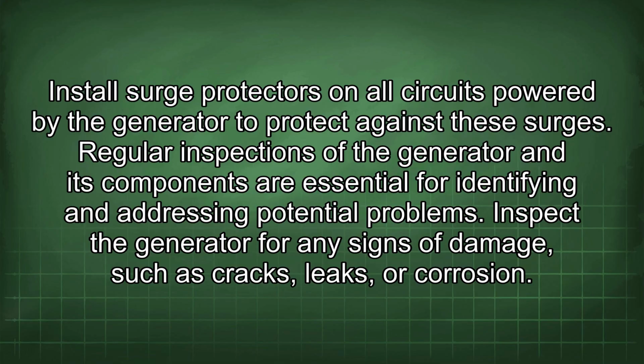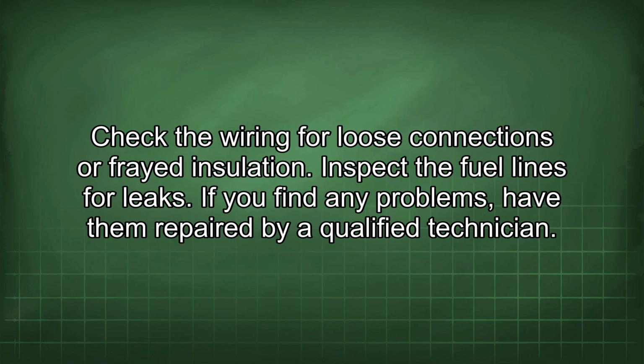Regular inspections of the generator and its components are essential for identifying and addressing potential problems. Inspect the generator for any signs of damage, such as cracks, leaks, or corrosion. Check the wiring for loose connections or frayed insulation. Inspect the fuel lines for leaks. If you find any problems, have them repaired by a qualified technician.